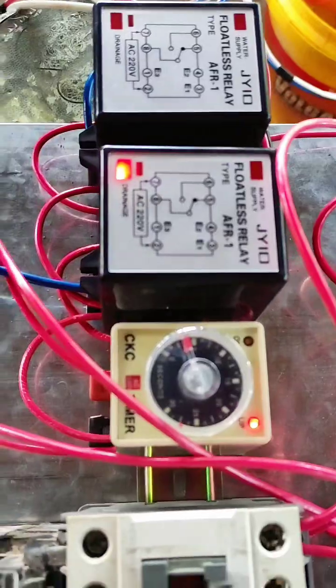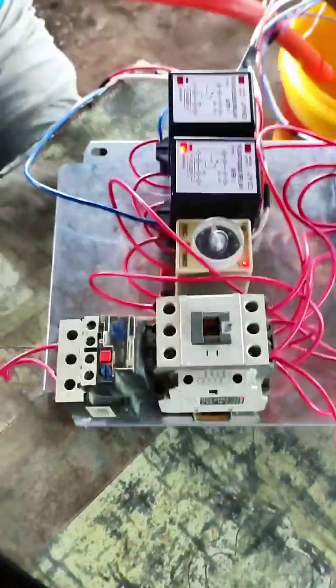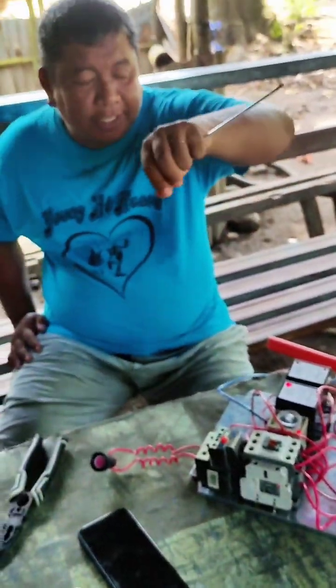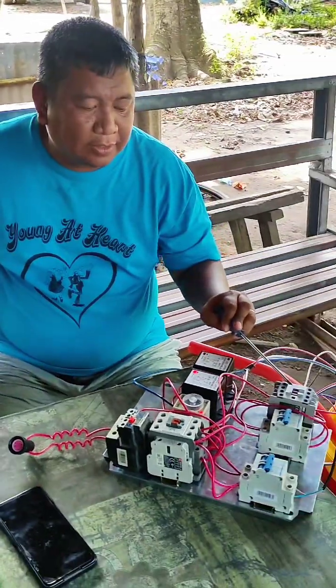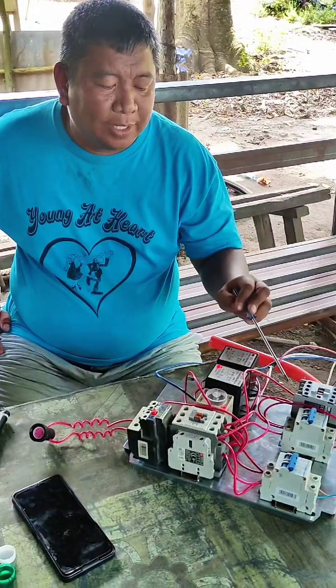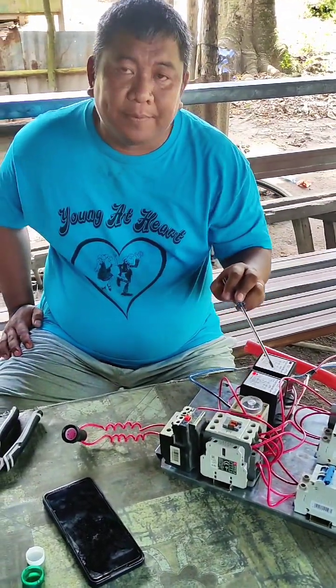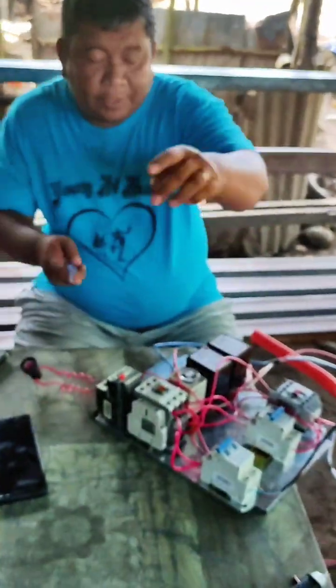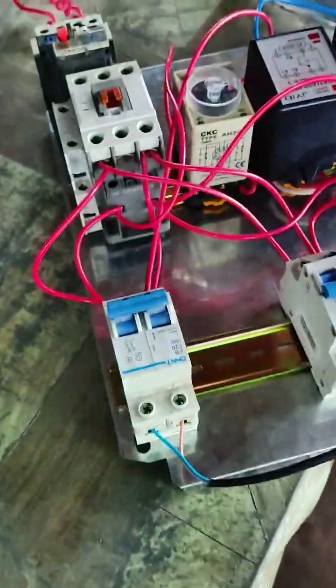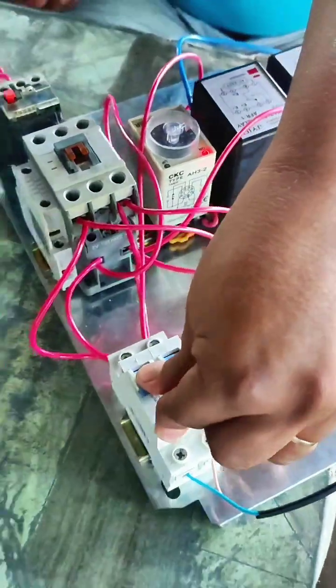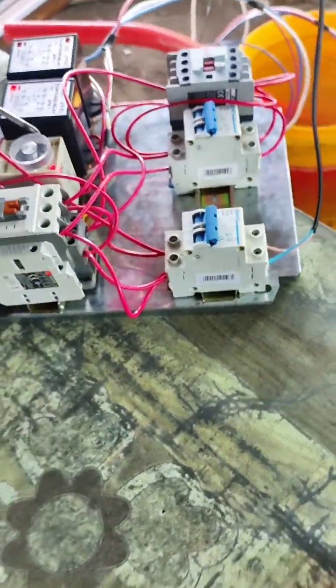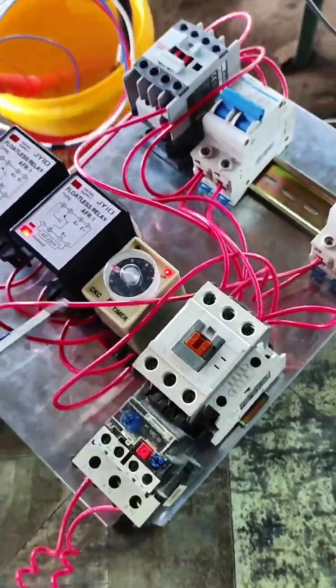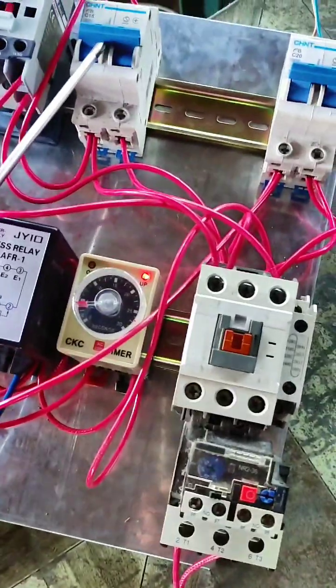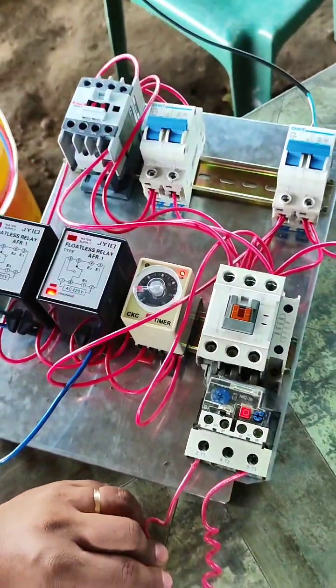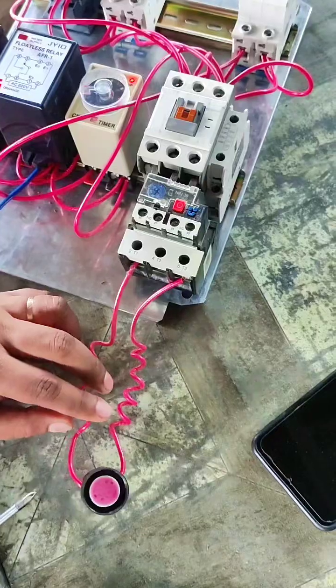That's good. And the second is this one. So we shift now to automatic, like this one. This contactor engages from normally closed, normally opens the circuit for this system. For example, this is off, right? The circuit is cut. You see this? This is the main line. This is cut. Everything is cut in there. So we put it on, and we wait for the timer. The timer goes on and engages in 5 seconds. So this automation is engaged because it's locked in automation, right? This light here simulates our engine. This is our main output.